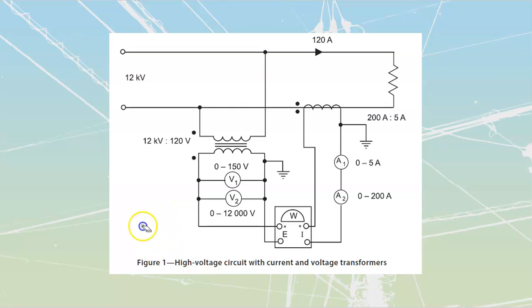Let me just erase a bunch of the extra stuff we don't need to see on here right now. And let's just verify that all of our dots are on the same line. This is my line that I'm choosing to identify. I'm just going to put an I over here for identify. I see that my PT has its dot attached to the identified. I see that my CT has its dot attached to the identified. And then on the other side of my PT, I see that it's got its dot attached to the identified section of the wattmeter. And on my CT, it's got its dot attached to the identified section of the ammeter over here. That's it. That covers us off for these components over here.